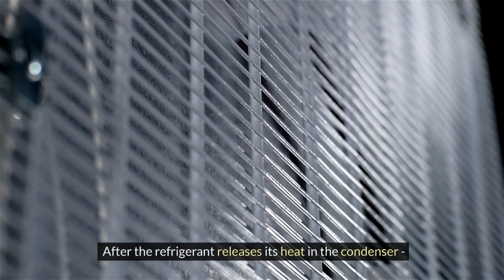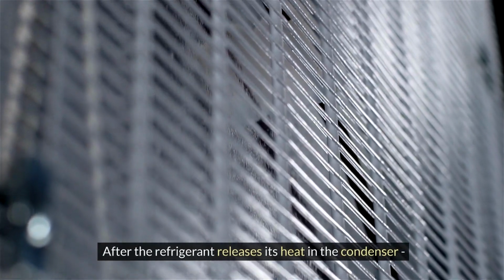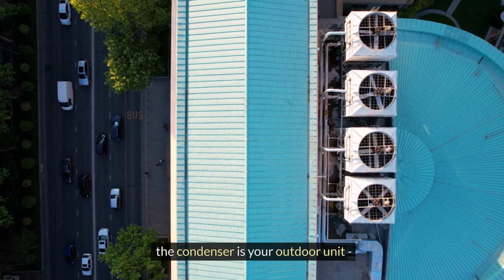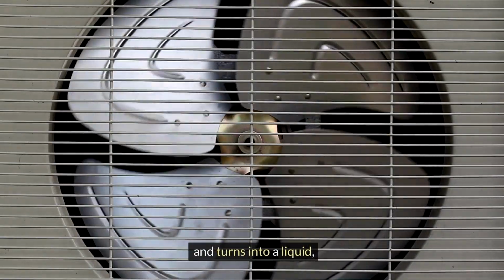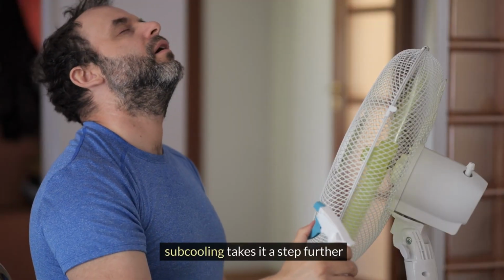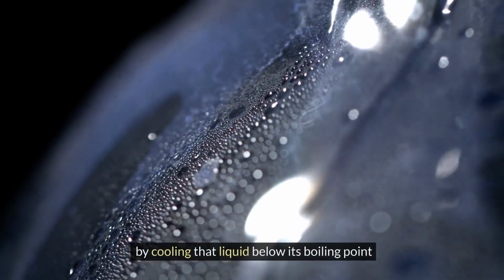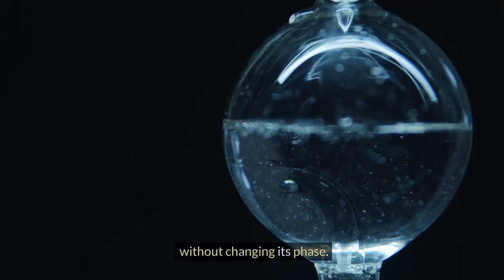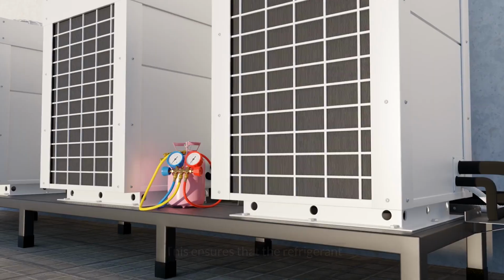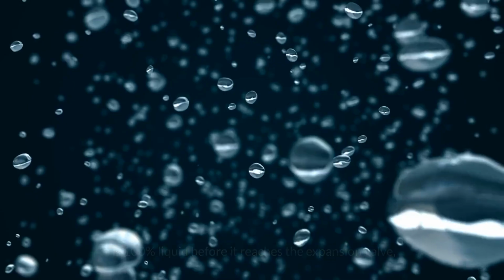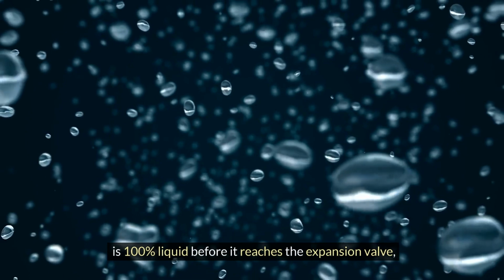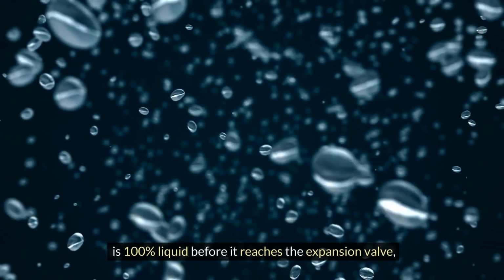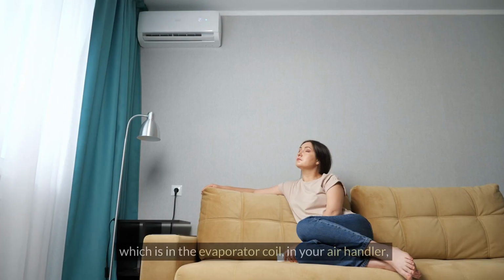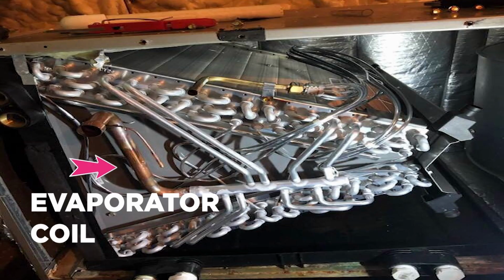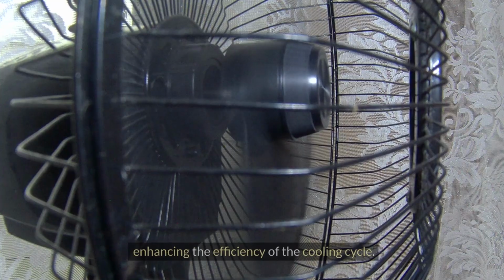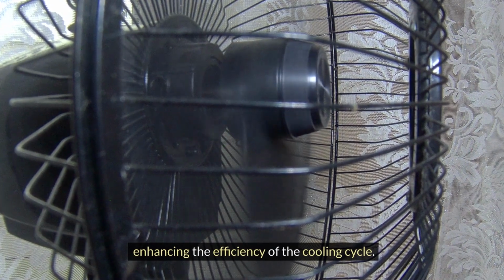After the refrigerant releases its heat in the condenser, which is your outdoor unit, and turns into a liquid, subcooling takes it a step further by cooling that liquid below its boiling point without changing its phase. This ensures that the refrigerant is 100% liquid before it reaches the expansion valve, which is in your evaporator coil in your air handler, enhancing the efficiency of the cooling cycle.